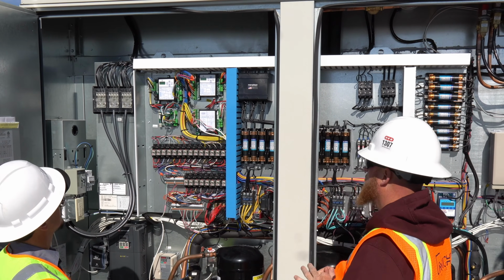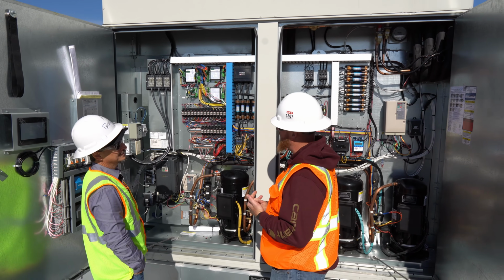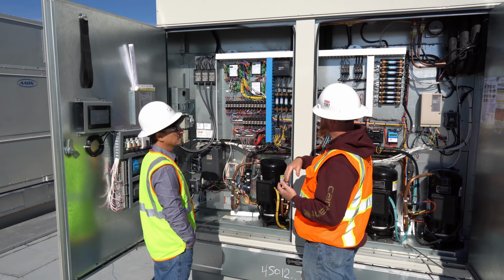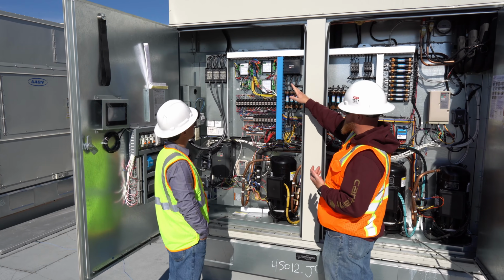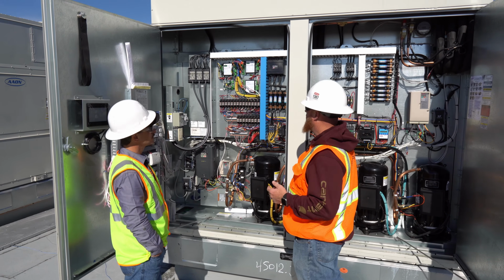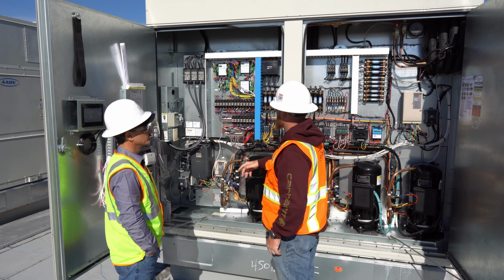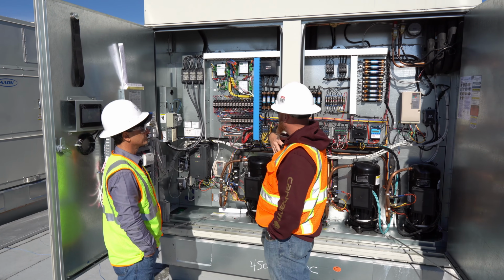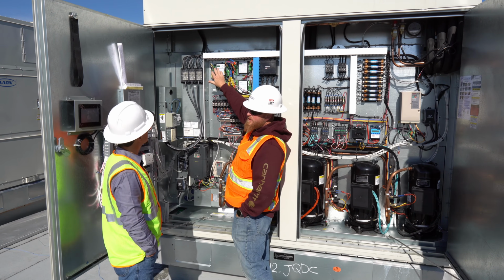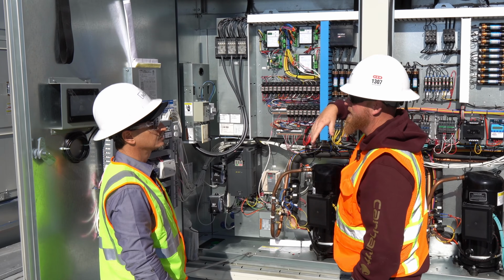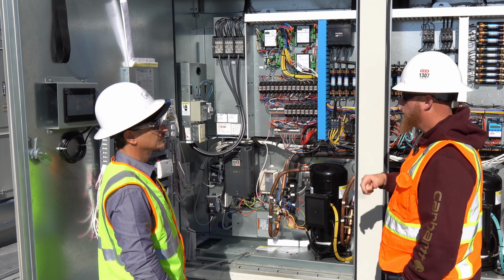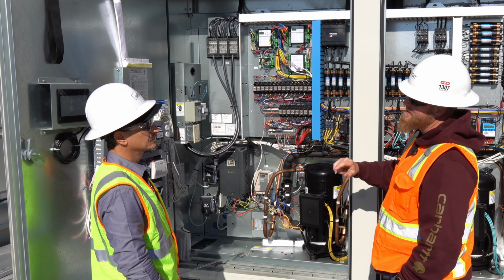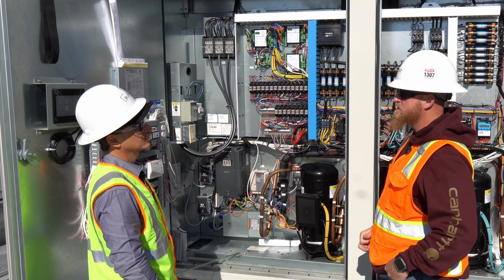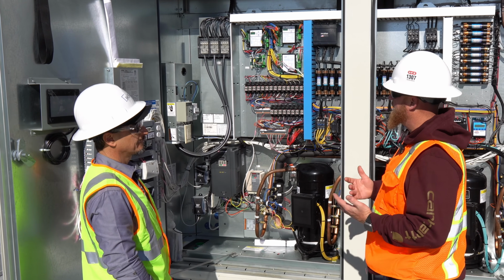It is. So we still use AAON's modulating hot gas reheat board. This one has head pressure control modules because of our water condenser, but we still use them, they still integrate. However, we send them set points, we reset variables, so when the reheat valve is looking for what set point to control to, we're actually passing that information into it.